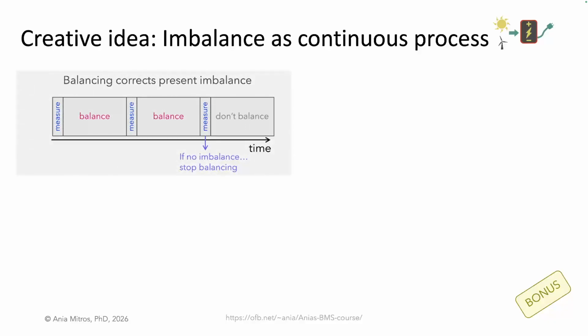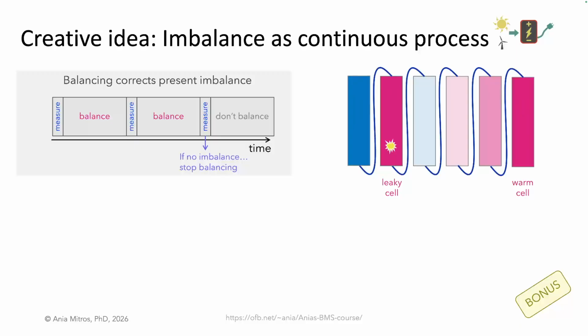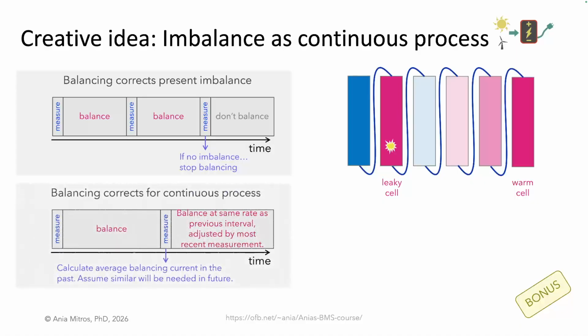Another idea that I once heard but didn't quite see brought into practice is thinking of imbalance as a continuous process. The standard approach is for balancing to correct the presently observed imbalance and then stop. We wait to balance again until the pack has imbalanced itself again. A past colleague observed that imbalance is a continuous process. If you have a leaky cell to correct for yesterday, that same cell will probably still have the highest self-discharge today. If yesterday the pack had a warm end and a correspondingly unequal self-discharge, that will probably still be true today. So, perhaps our balancing algorithms should account for that.